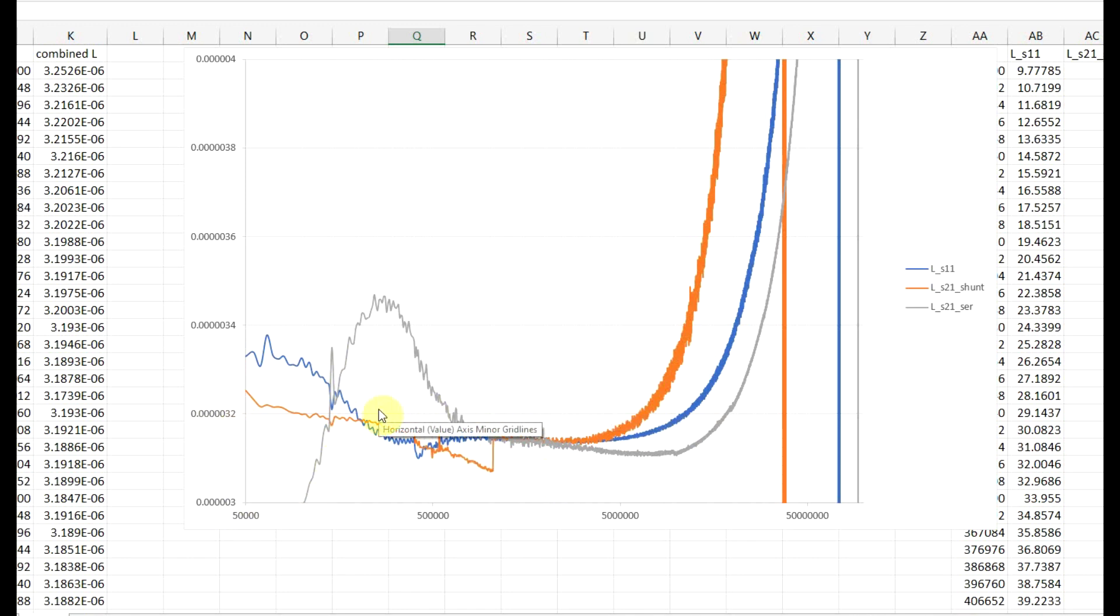So, at very low frequency, the series through method is giving this hump, so this is definitely not correct. We are seeing a hump, at least at very low frequency, even with the single port measurement, but the shunt through measurement is the only one that is giving a more or less flat response. So, at low impedances, at low frequencies, this is more accurate.